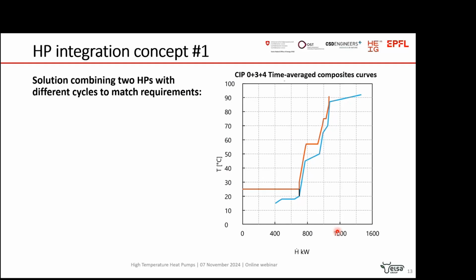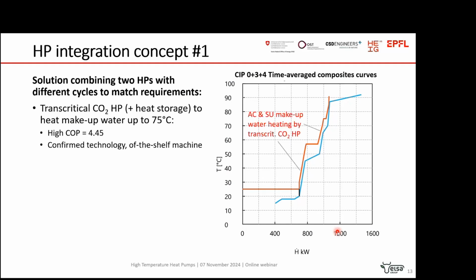So the solution or integration concept that we can derive from this composite curve, in fact, combines two different technologies or cycles. One is a transcritical CO2 heat pump for heating the makeup water with a high COP, and this is confirmed technology, an off-the-shelf machine.